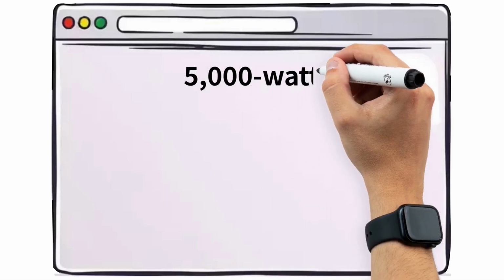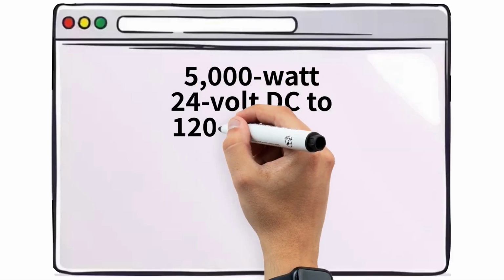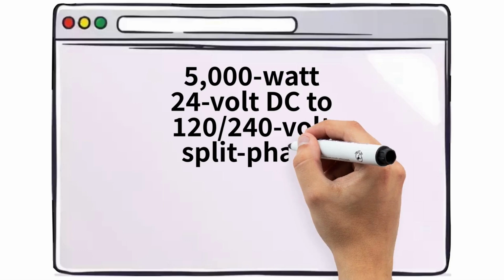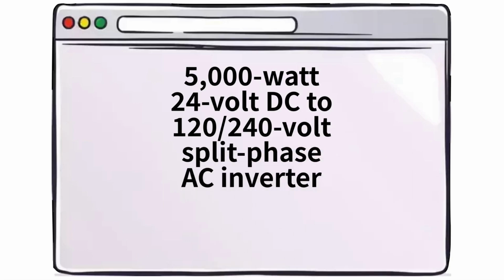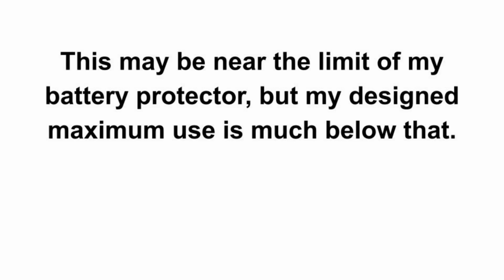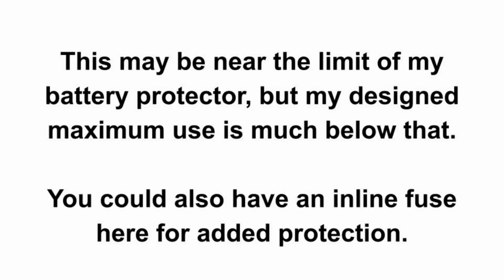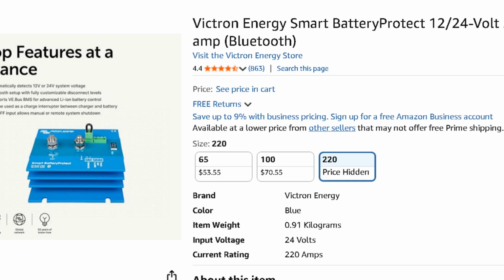The largest load on my system would be my 5000 watt 24 volt DC to 120/240 volt split phase AC inverter, which maxes out at 192 amps. This may be near the limit of my battery protector, but my designed maximum use is much below that. You could also have an inline fuse here for added protection. There is a link in the video description to the Victron Energy Smart Battery Protector on Amazon, so you can look at what it can do.